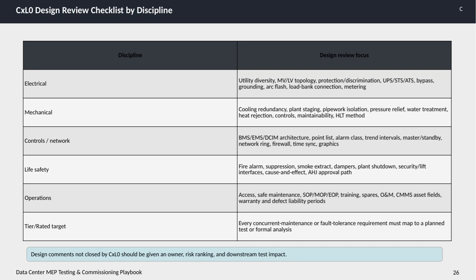For mechanical, attention must be given to cooling redundancy and plant staging, which are vital for maintaining system uptime. Pipework isolation, pressure relief, water treatment, and heat rejection methods are crucial for operational stability.